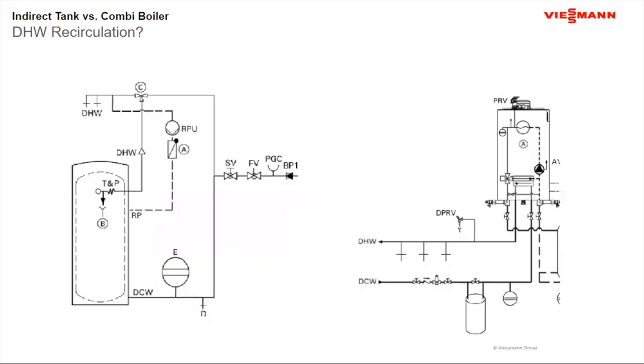Okay, questions come up about recirculation. Domestic hot water recirculation with a tank style water heater? Absolutely. I can do recirculation because I can recirculate off of the volume of the tank. And then what will happen is it'll just increase the frequency that the boiler runs and recovers the water heater.